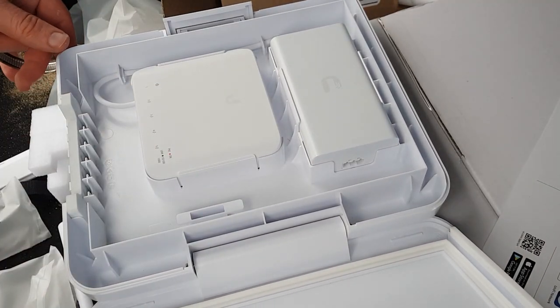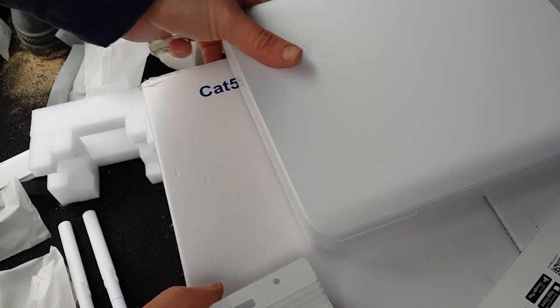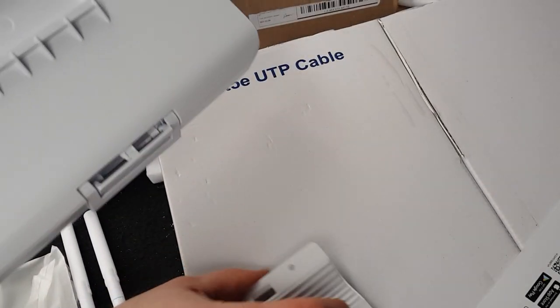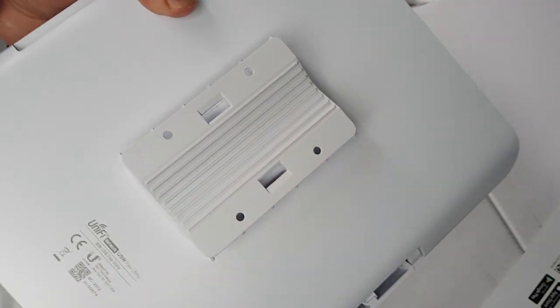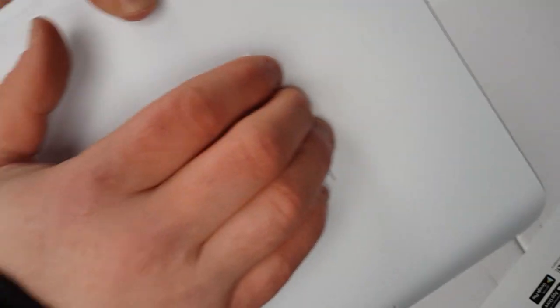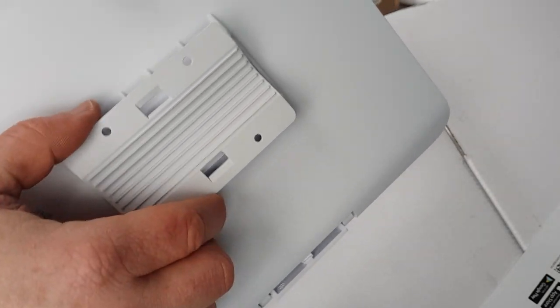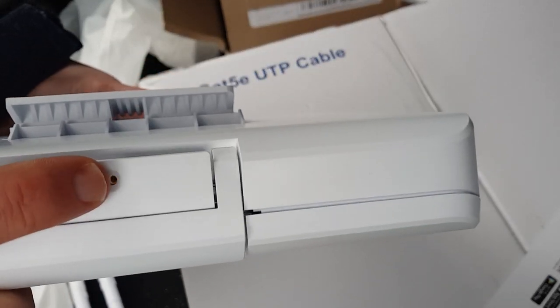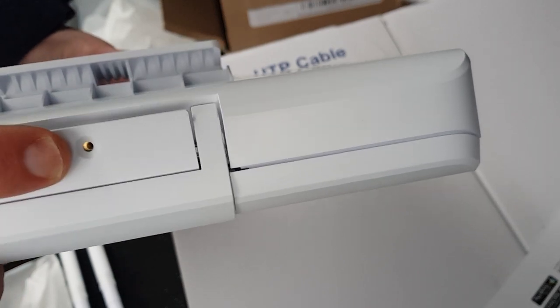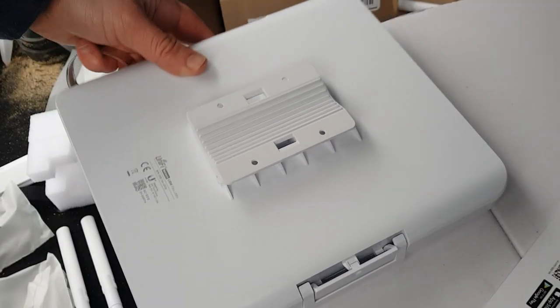Once you've got your injector and your switch in, depending on how you're going to mount your Flex Utility box, you can either use the mount on a pole or you can actually screw it onto a flat base. One thing to note: there is no actual security lock on this, which is kind of a bit of a disappointment. That is locked in place, but there is nothing to stop anyone coming along and lifting it off that mount. So Ubiquiti — next time, maybe something under here would be a useful idea, so that you can slide and screw in or lock in place to stop anyone tampering with this. There is a screw that goes in there to stop people opening the unit, but there is nothing to stop people just generally coming along, lifting the unit off and running away with it. Just something to be aware of with these units.